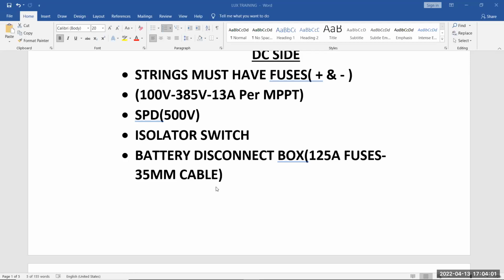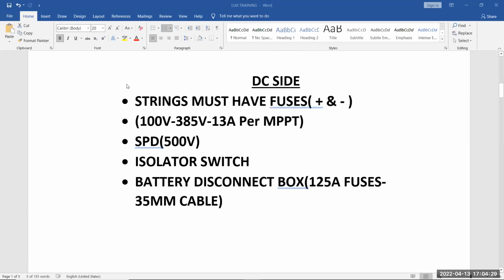We recommend on a 5 kilowatt inverter, 125 amp fuse links for the batteries and a 35 mil battery cable. The battery cable is going to depend on the length that you run. If you're going to run a few meters of battery cable, you're going to need thicker cables to run that current over a longer distance. So this is my DC side, quickly explained.